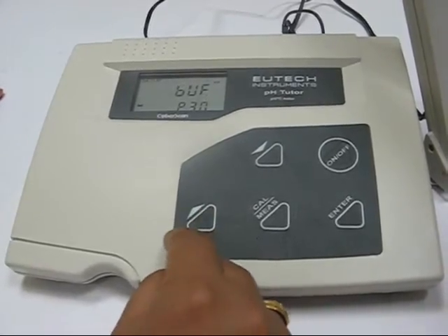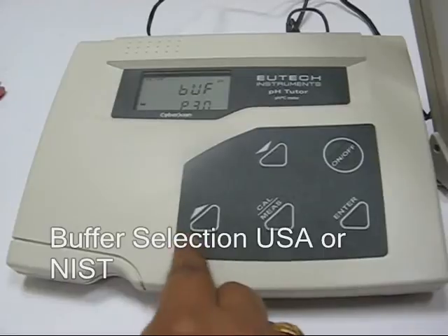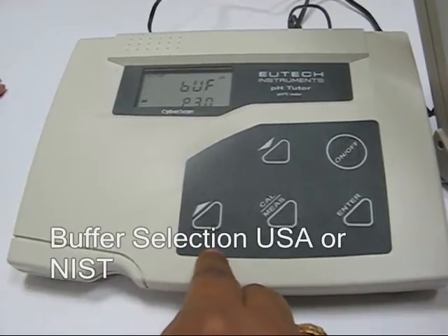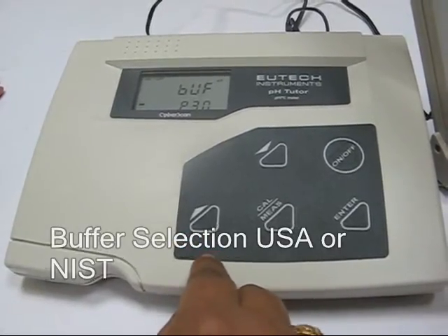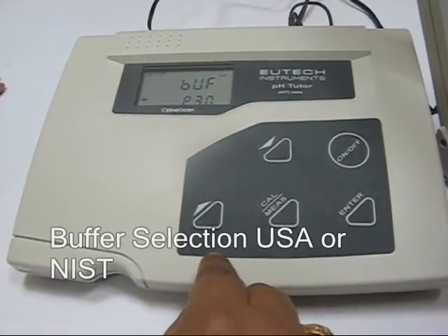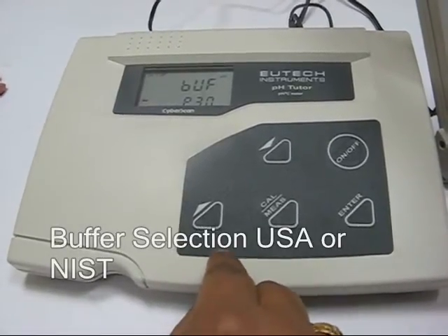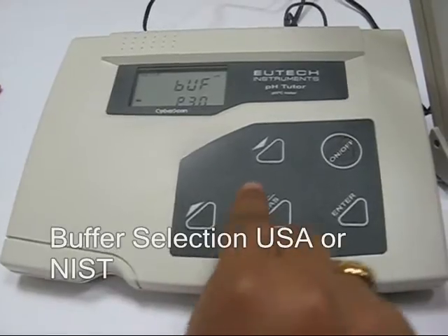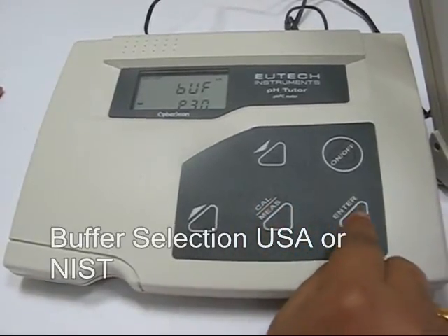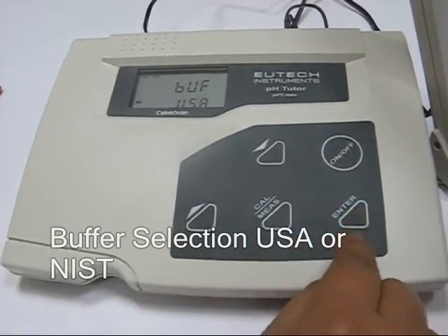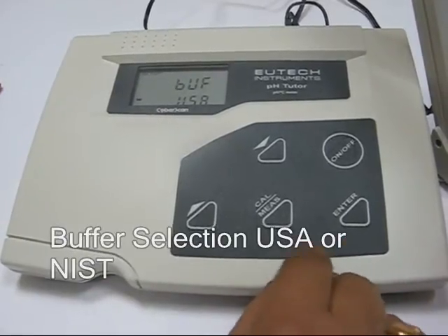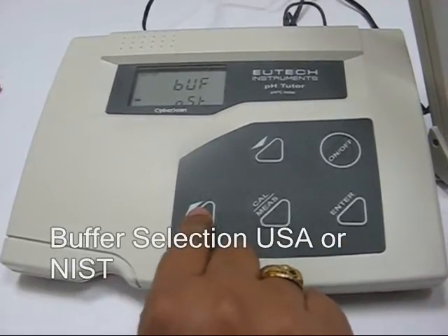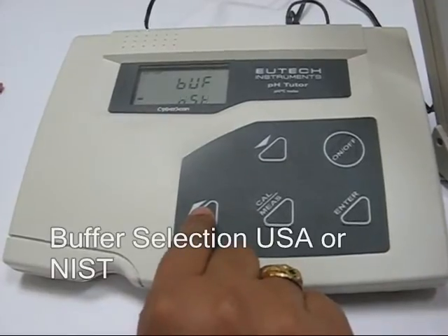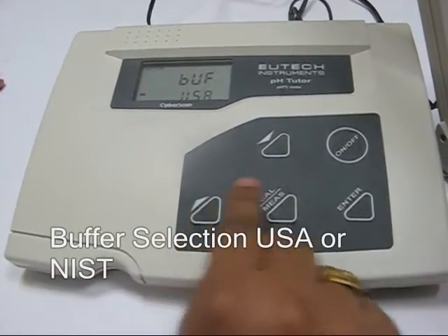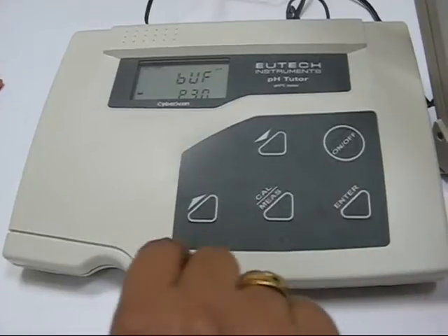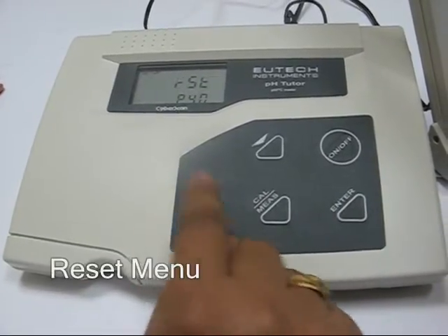and the up key to go to program menu 3.0. Now this menu is for selecting the type of buffer that you're going to use for calibration. There are basically two types of buffers. One is called the USA buffer, and the other one is called the NIST buffer. By pressing the enter key, you will get in to the setup menu. Now by pressing either the up or down key, you can toggle between USA and NIST. Let's leave it at USA for the time being and press the enter key. Now press the up key to go to the last menu, which is the reset menu.